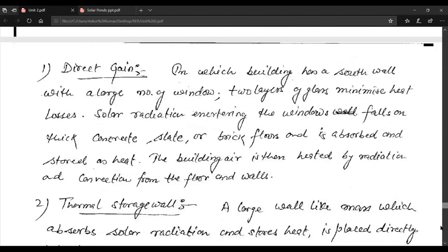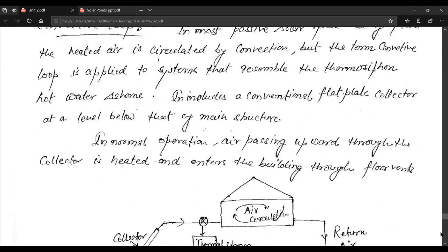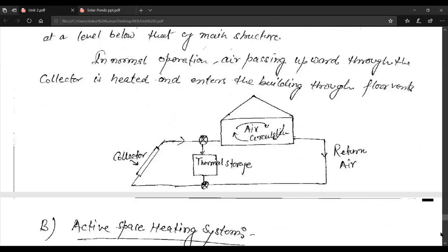In most passive solar space heating systems, heated air is circulated by convection. The convective loop system resembles a thermosiphon hot water scheme and includes a conventional flat plate collector at a level below the main structure. In normal operation, air passing upward through the collector is heated and enters the building through floor vents.